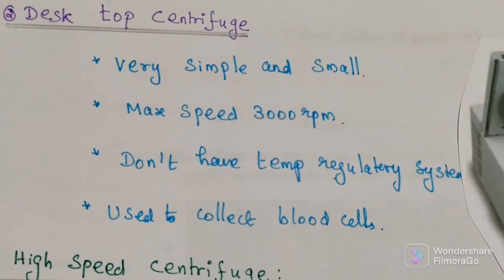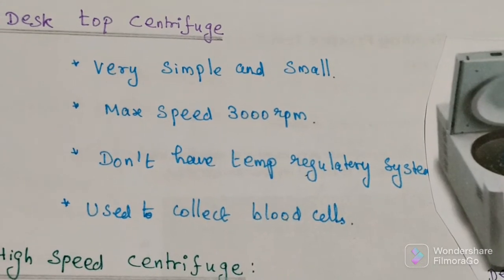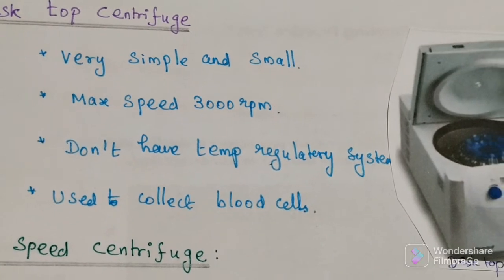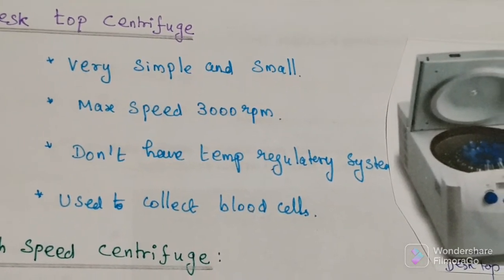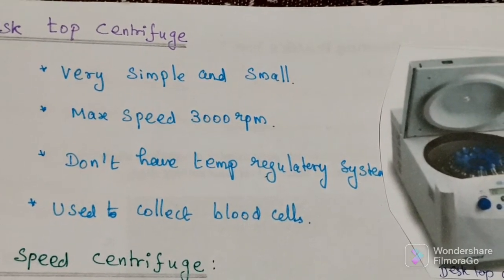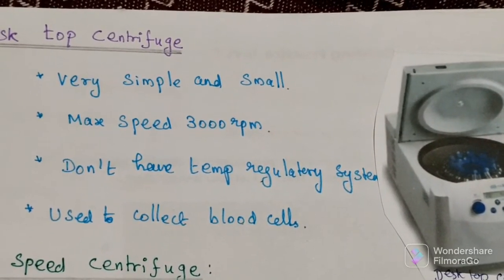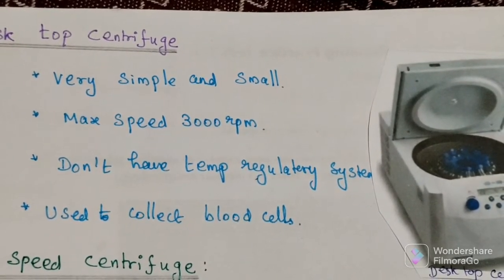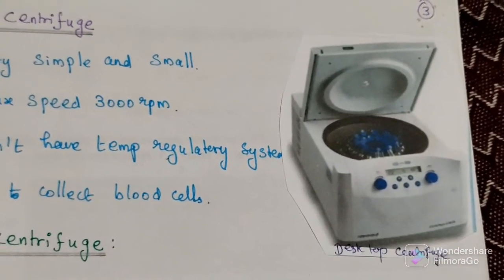Another example of a small bench centrifuge is the desktop centrifuge. It is a very simple and small centrifuge with a maximum speed of around 3,000 RPM. This one does not have any temperature regulatory system. It is used in small laboratories, normally to collect rapidly sedimenting substances such as blood cells.